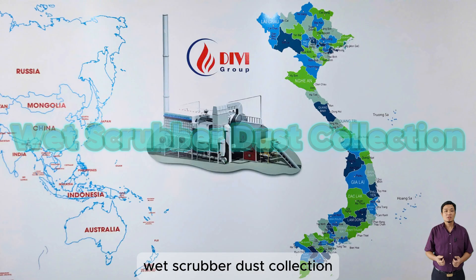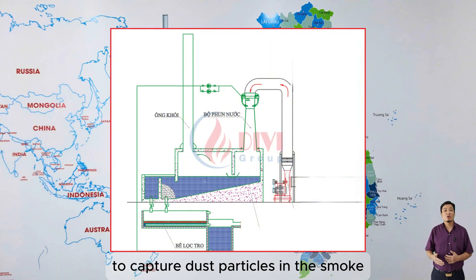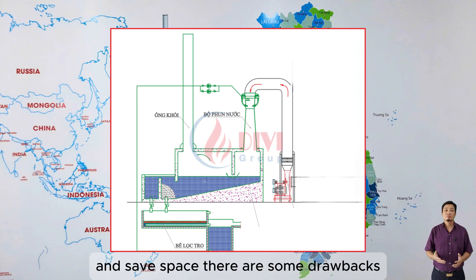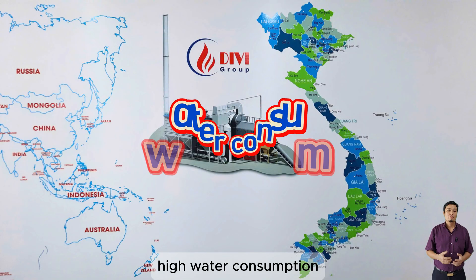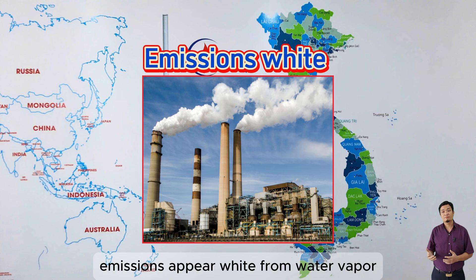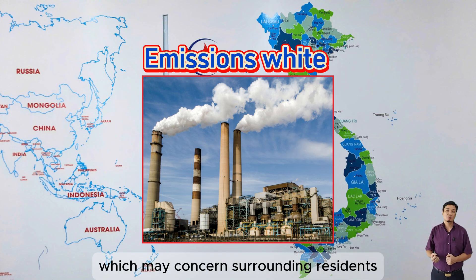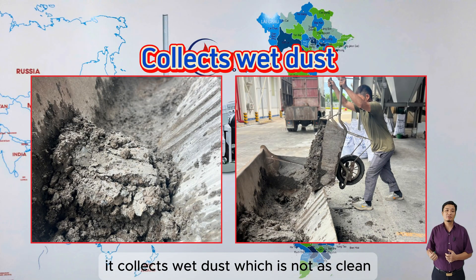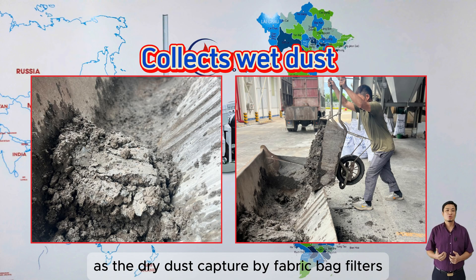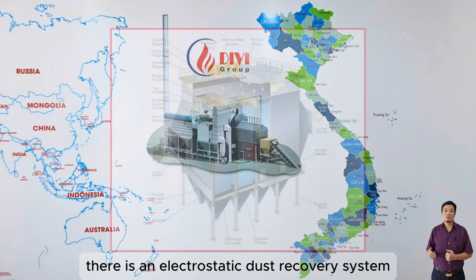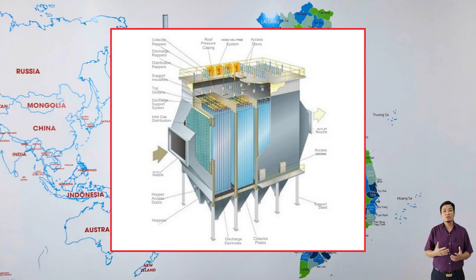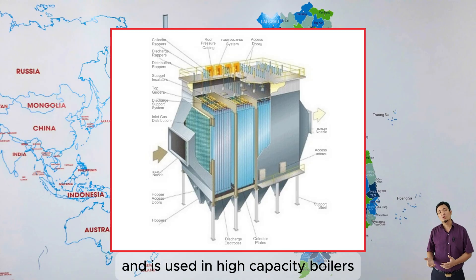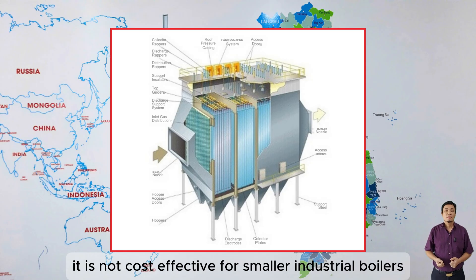Wet scrubber dust collection: this system uses water spray to capture dust particles in the smoke. While it has good dust collection efficiency and saves space, there are some drawbacks: high water consumption, emissions appear white from water vapor which may concern surrounding residents, and it collects wet dust which is not as clean as the dry dust captured by fabric bag filters. Additionally, there is an electrostatic dust recovery system, which typically has a very high investment cost and is used in high capacity boilers. It is not cost effective for smaller industrial boilers and will not be covered in this video.